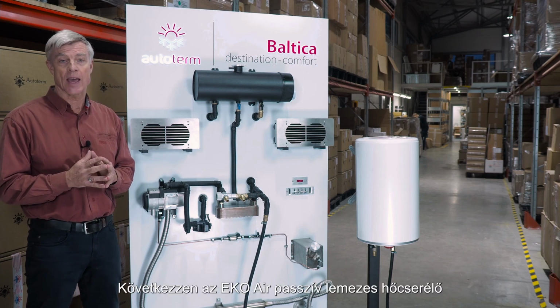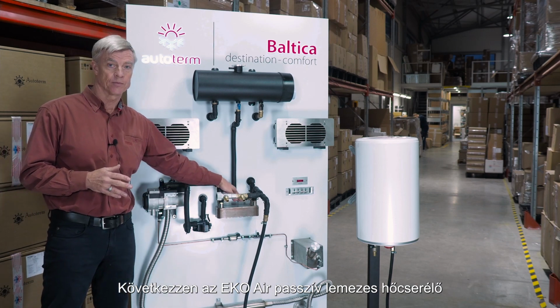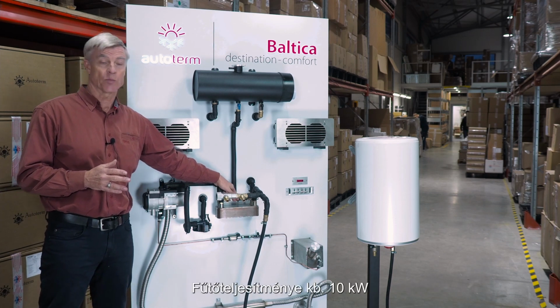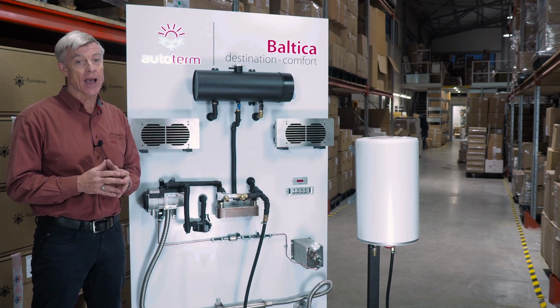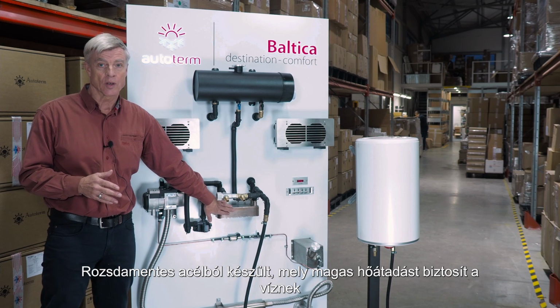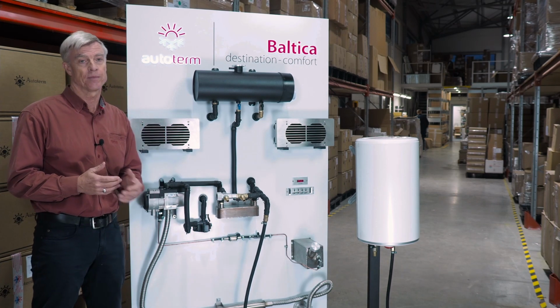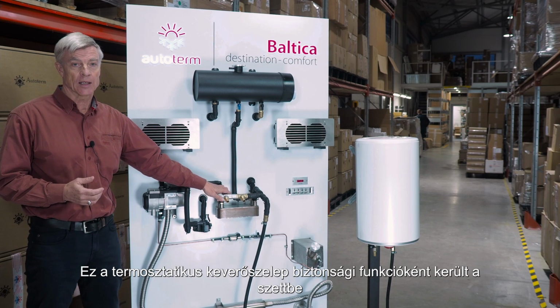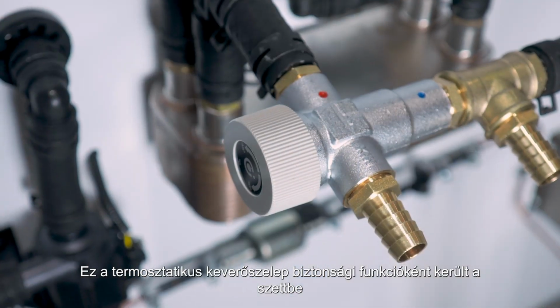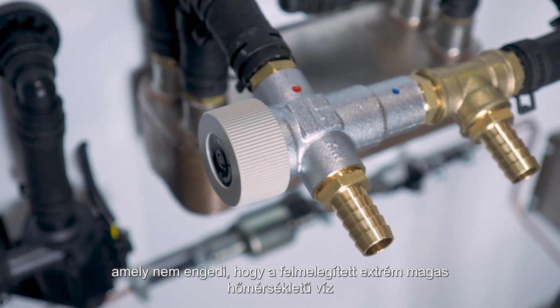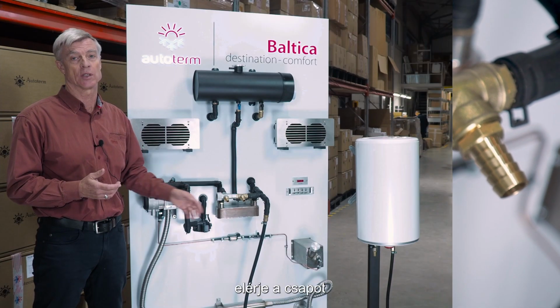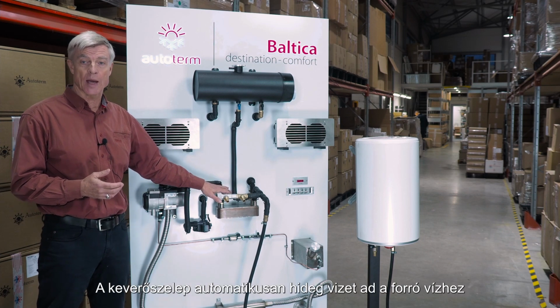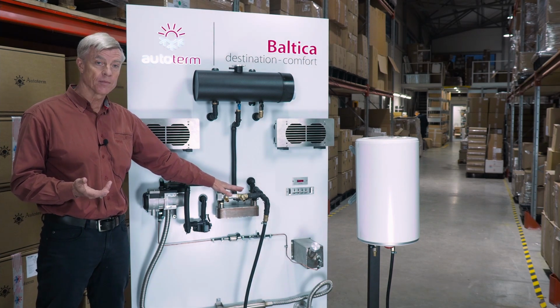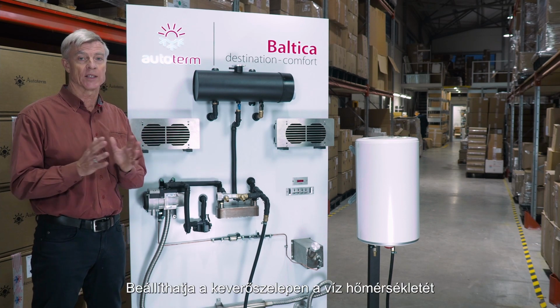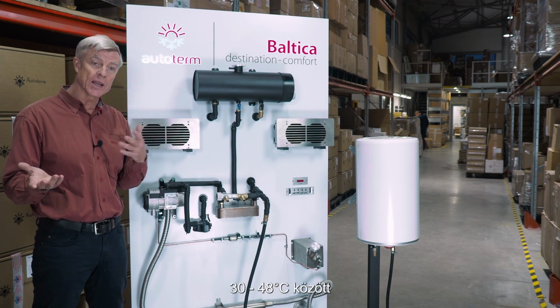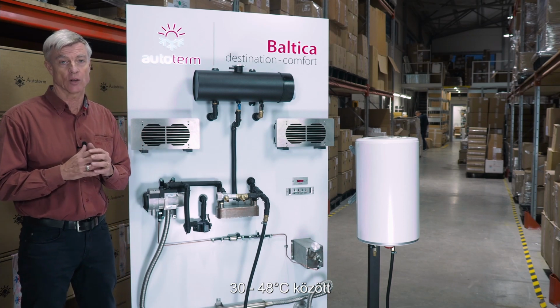Next, we have the EKO Air Passive Plate Heat Exchanger. For domestic water heating, it has approximately 10 kilowatts of heating power, and its stainless steel body ensures high heat transfer to the water. This thermostatic mixing valve is added as a safety feature that will not allow the heated water to reach a tap or faucet at extremely high temperatures. The mixing valve will automatically add cold water to the hot water. You have full control and can set the temperature on the valve within range from between 30 and 48 degrees Celsius.